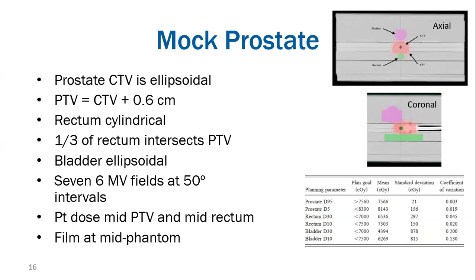And then you also have a bladder target that is also an ellipse. They plan these with 7 6MV fields at 50-degree intervals, took the point dose at the mid PTV and at the mid rectum, right? So if you remember back to that phantom that we used, that had that sort of array of inserts where we could put the chamber in many different places. So we would put the one chamber in a point that corresponds to the middle in this case, because the PTV is right in the middle of the phantom. And then the rectum would just be a little bit inferior of that. You could actually measure and see how inferior, but probably it would be in the insert directly below the PTV. And then the film at mid phantom, like usual.